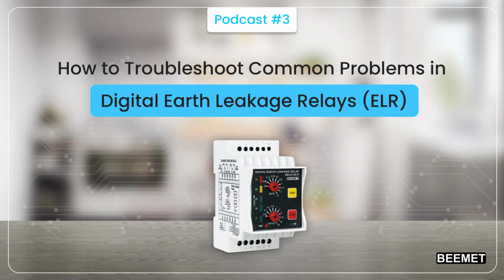Unstable or floating readings. This happens when the reading on the screen keeps going up and down for no reason. It generally means that there is noise interference or bad grounding. What to check? Tighten CT secondary wires. Reset the zero reading on the relay. Use a meter to check the backup power source.